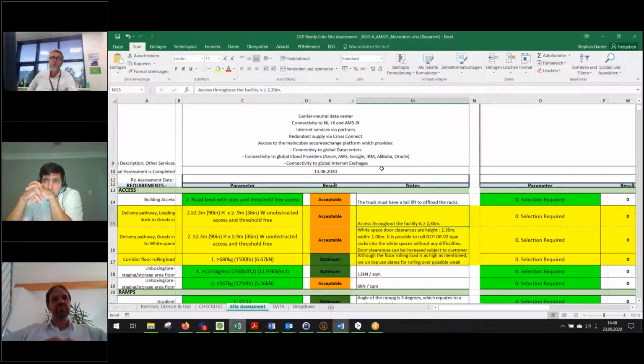So to simplify, the answer is we can build racks up to 20 kilowatt, and depending on the room, at the end of the day, the number of racks is limited to the cooling capacity in that particular room. I will cover some of that in one of the slides regarding the OCP setup that we have already running. If we need more detail, we take it offline as well. Joris, I would have been quicker than you, but that's fine. Brilliant. That's more or less what I wanted to say.